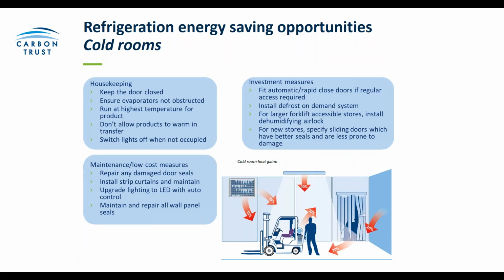In terms of your cold rooms, again, housekeeping, it's good to make sure you have good door management. So this essentially means that you're keeping the door of the cold store closed wherever possible. And this keeps warm air and, importantly, moisture out and brings down your energy costs. Making sure that the airflow from the evaporators isn't obstructed, and run the cold store at the highest possible temperature for the product that you're storing. Ensure the product load in your cold room hasn't warmed up by being left in an ambient temperature area. Again, this is the same as with the display cabinets. And again, making sure that lighting isn't being used where it's not necessary.